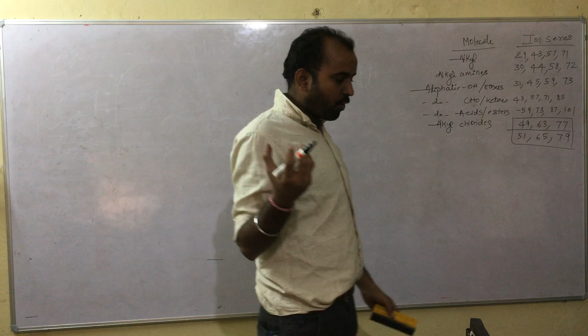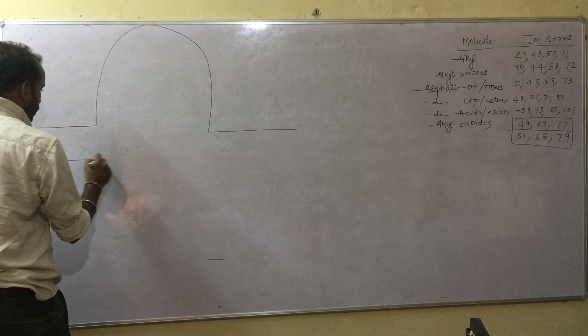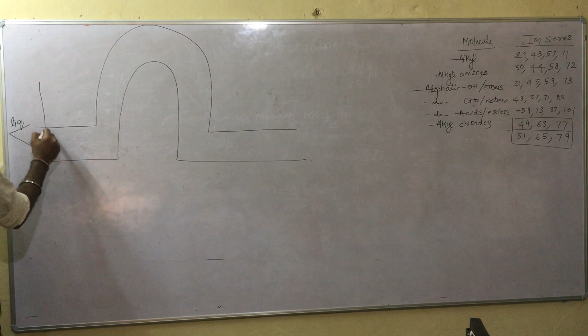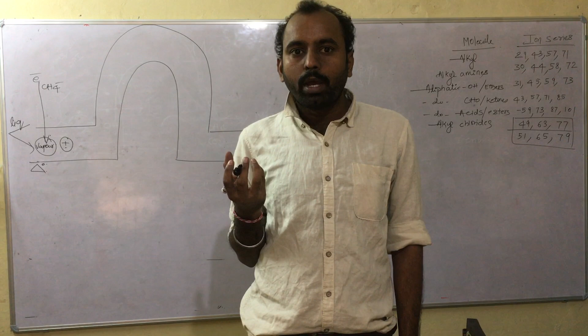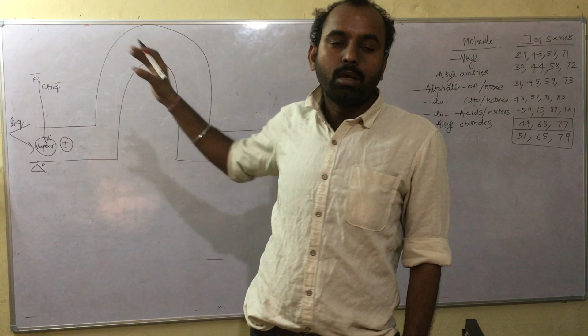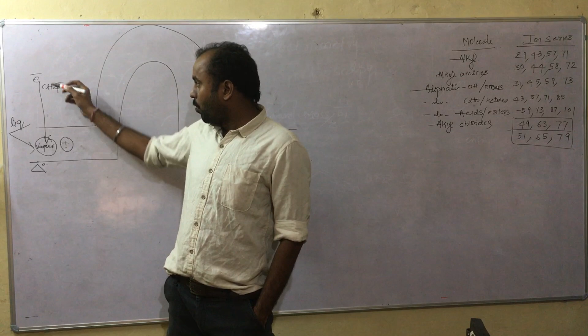Now let us see a schematic representation of a mass spectrometric instrument, how it looks. For mass, once you enter your liquid sample, this is your liquid sample entering into the analysis. Now you heat it, converting the liquid into vapor. Now the vaporized sample is bombarded with an electron or methane gas to convert the neutral molecules into radical cations, and these cations are analyzed based upon their mass to charge ratio. This is the fundamental. I am introducing the liquid sample and heating it so that it gets vaporized.